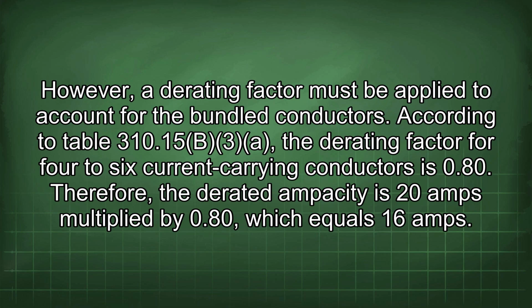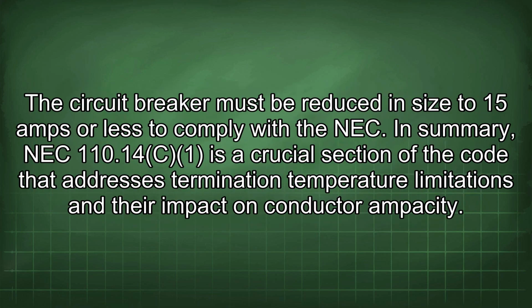According to Table 310.15(B)(3), the derating factor for 4 to 6 current carrying conductors is 0.80. Therefore, the derated ampacity is 20 amps multiplied by 0.80, which equals 16 amps. The circuit breaker must be reduced in size to 15 amps or less to comply with the NEC.